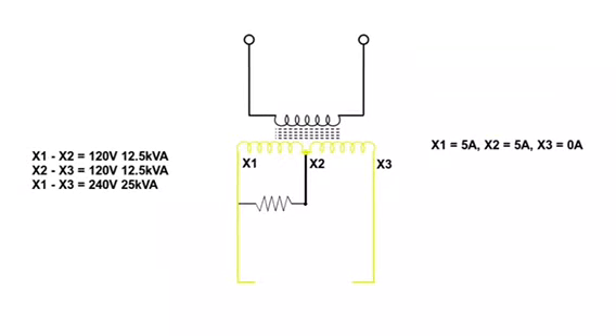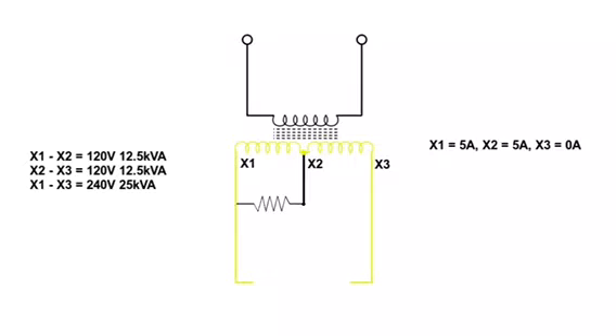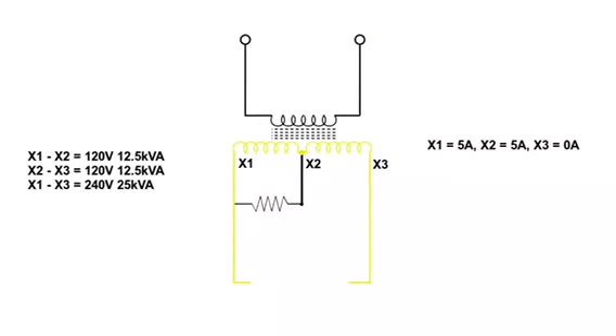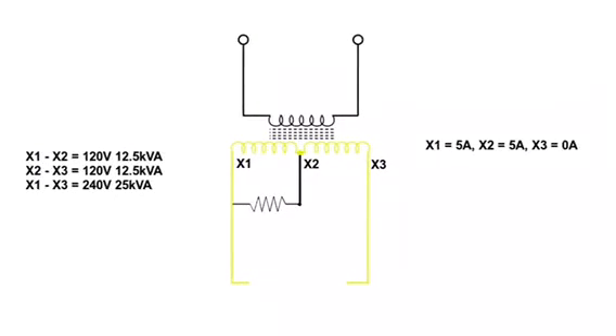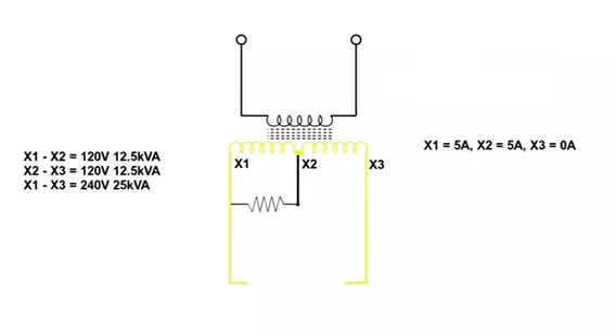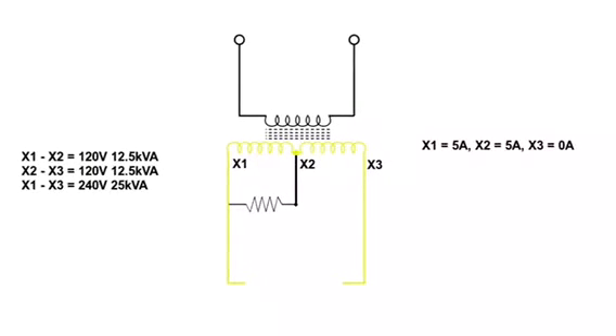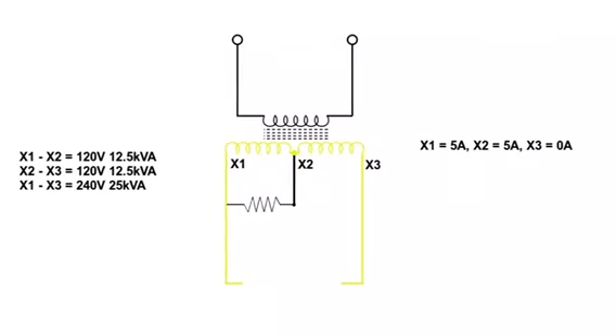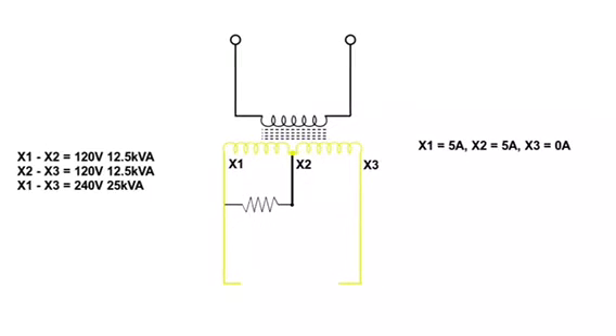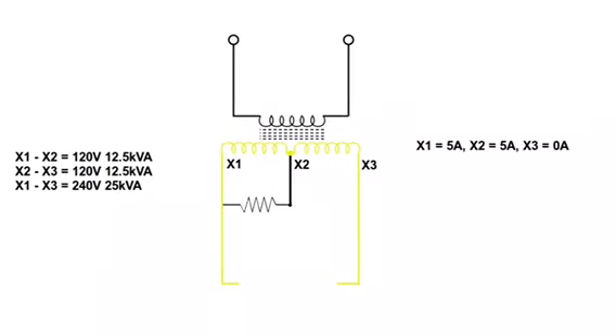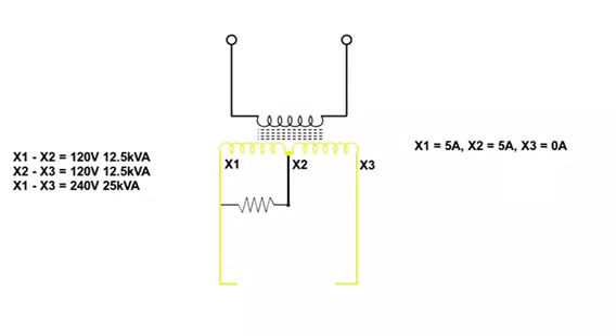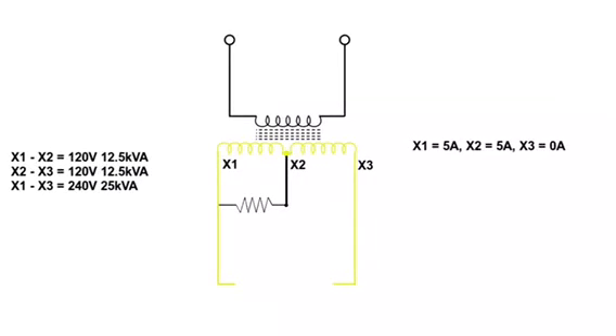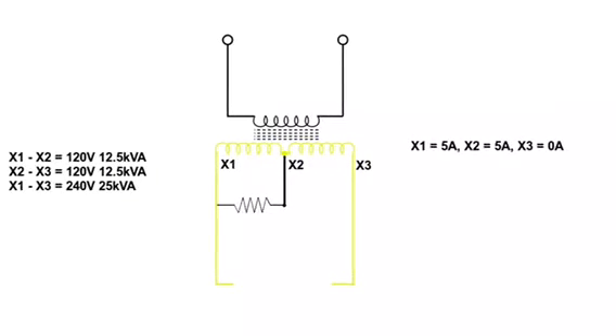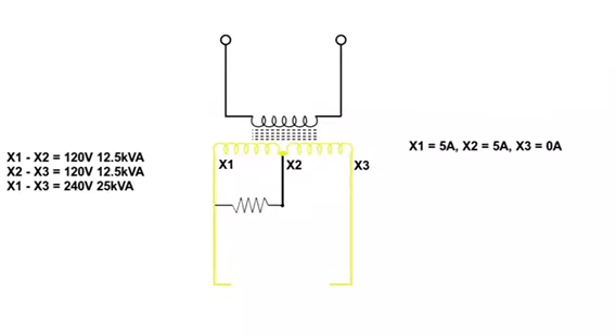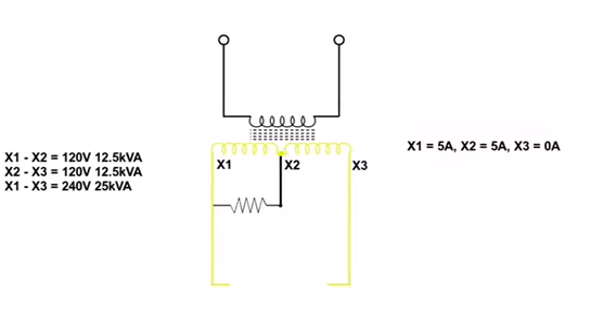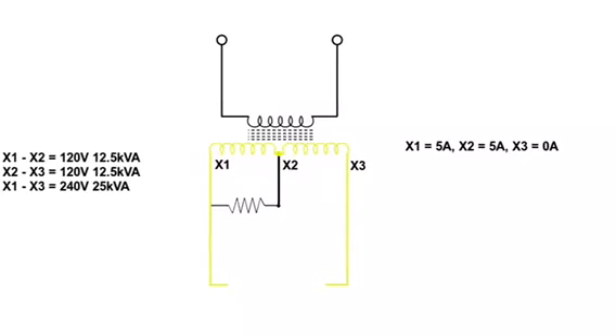If you were to take a clamp-on amp probe and measure the amps at terminal X1, which is actually line 1 inside your breaker panel, you will see that there's a 5 amp load. If you move that same amp probe over to the neutral, going outside up your service into the transformer, you will see 5 amps. Now moving the amp probe over to X3, you will see no amps, because there is no load in this drawing on the X3 terminal or L2.